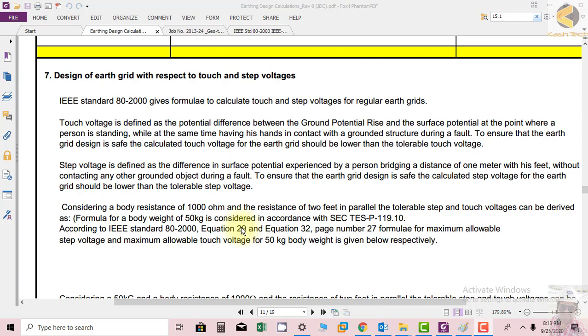This potential difference occurs where a person is touching and the surface. This potential is called touch potential when having hands in contact with a grounded structure during a fault. To ensure that the earth grid design is safe, the calculated touch voltage for the earth grid should be lower than the tolerable touch voltage.